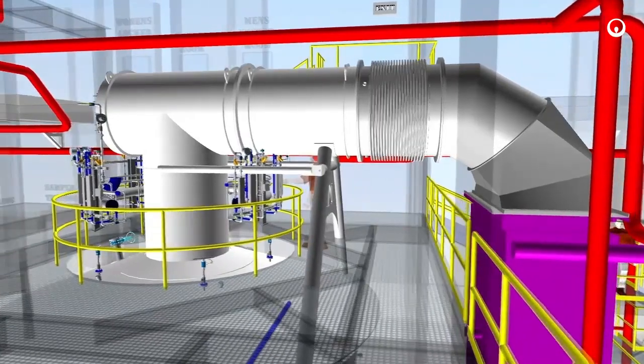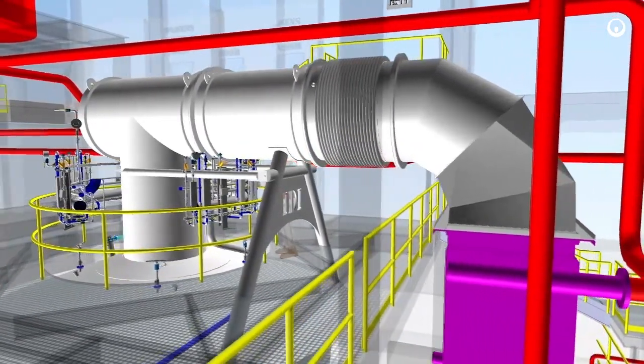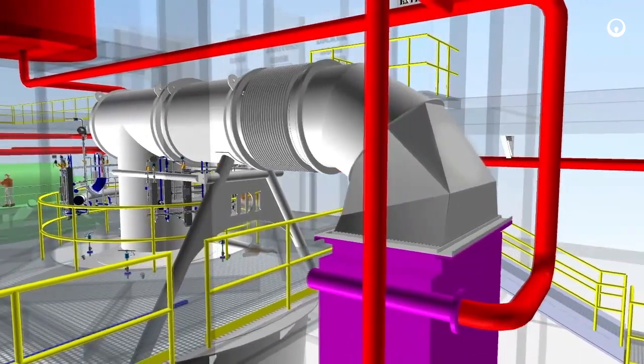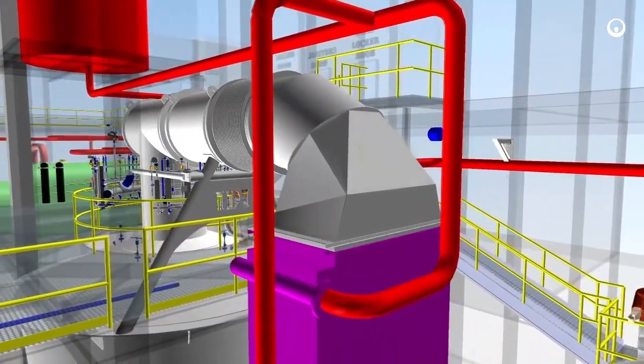Hot flue gas from the reactor first passes through the thermal oil economizer for energy recovery. Enough heat is recovered from flue gas via the circulating thermal oil to thermally support the thermal system.